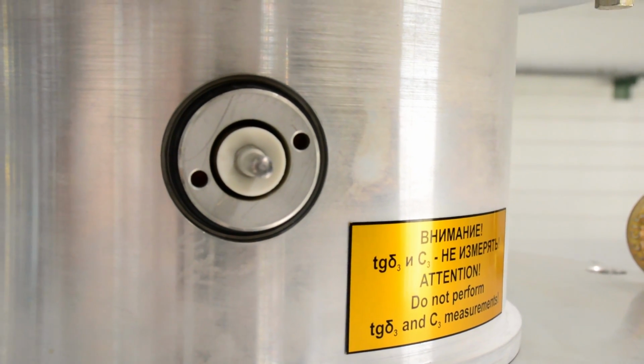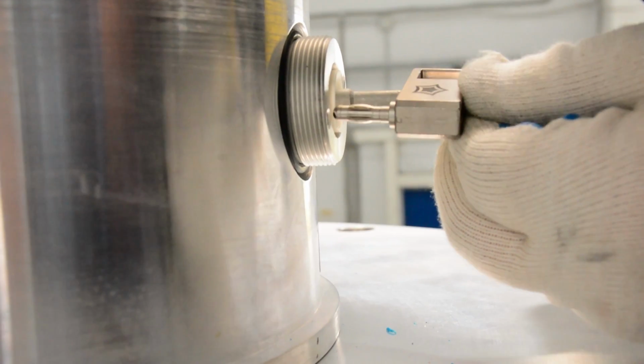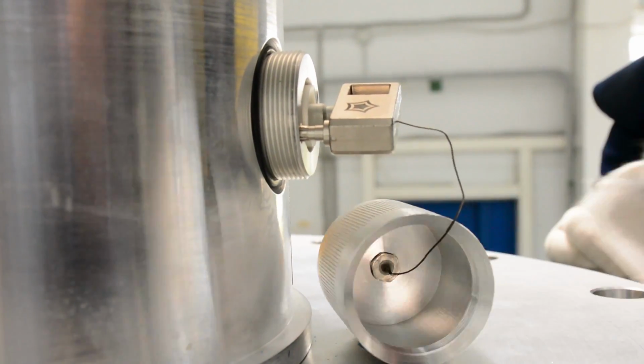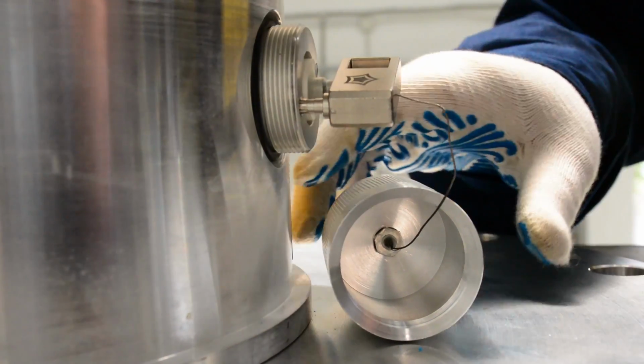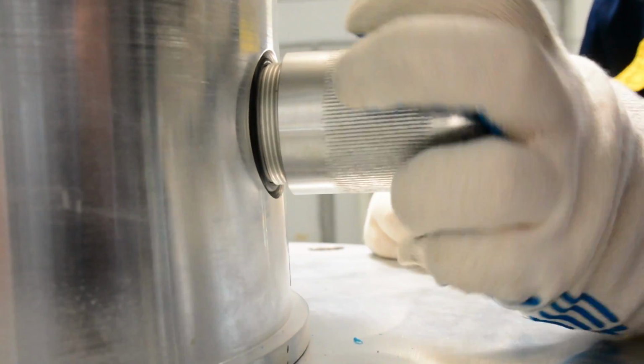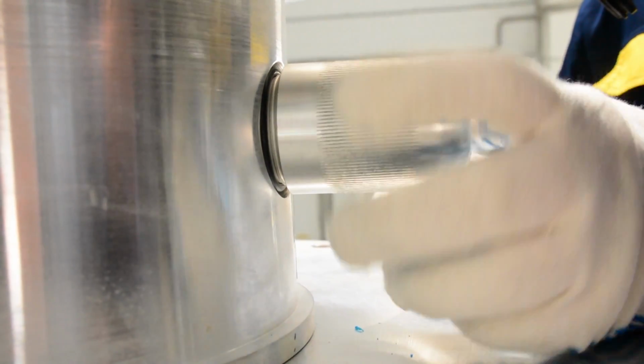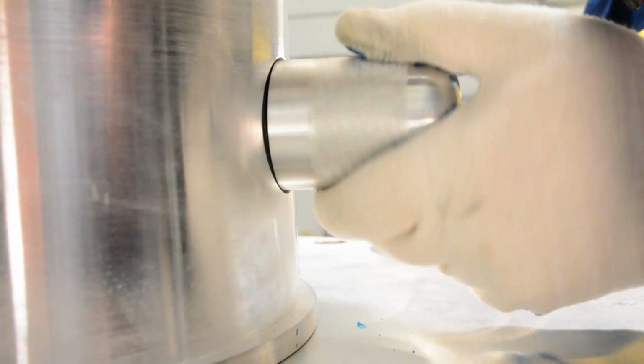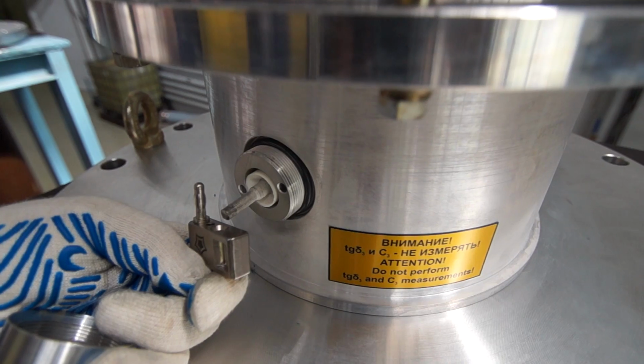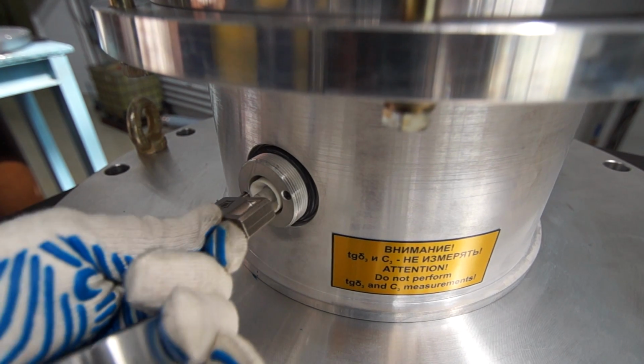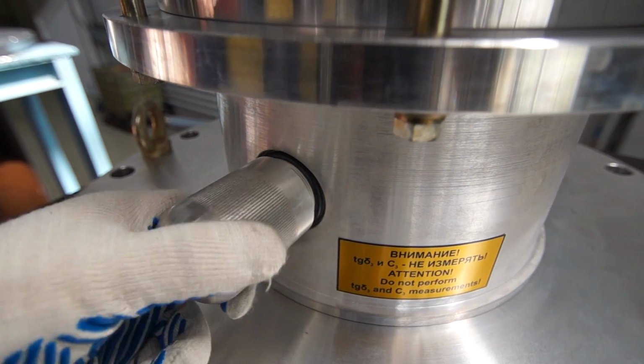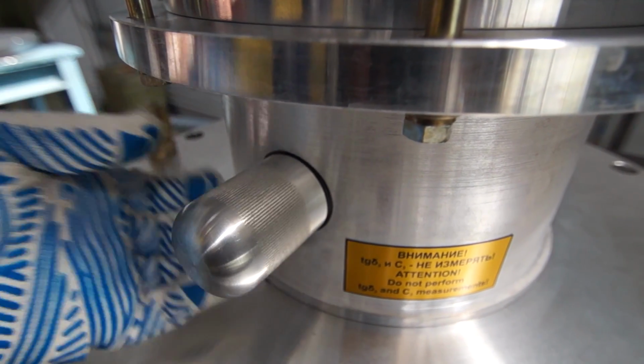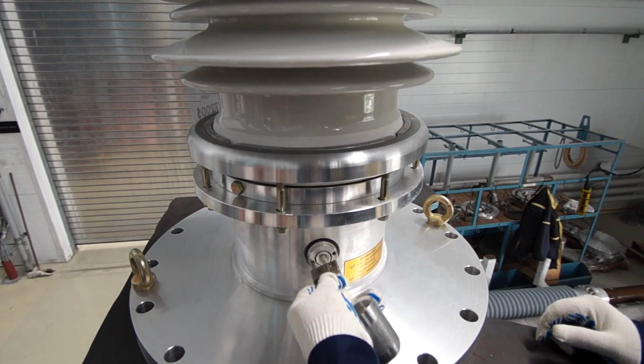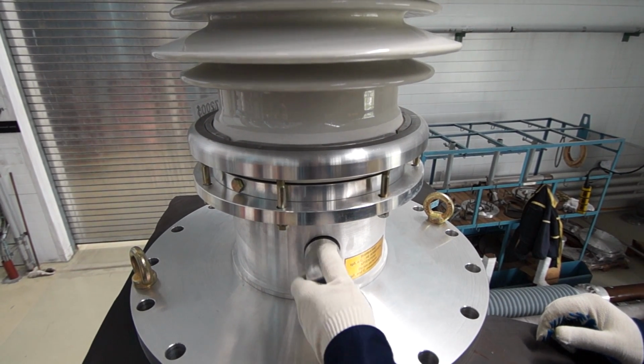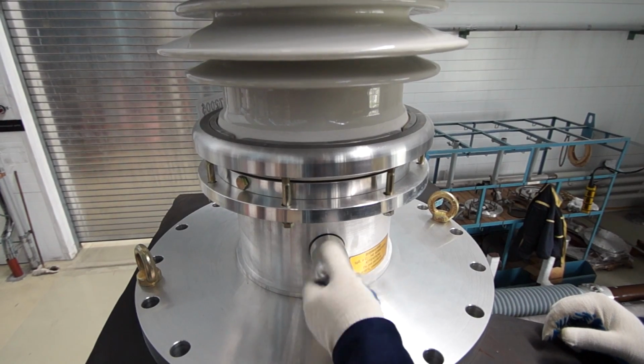Otherwise, should a high-voltage bushing be energized, the ungrounded pin of the test tap would receive approximately 50% of the voltage applied to the contact terminal, and that would invariably damage the test tap soon, leading to the complete breakdown of the high-voltage bushing. In order to ground the test tap, the multi-contact should be inserted so that the central hole of the lead went on the pin and the spring-loaded contact matched against the hole in the test tap body. At this moment, visual and tool control of the grounding reliability is possible, although with the proper installation of the multi-contact there is no need in the operation.